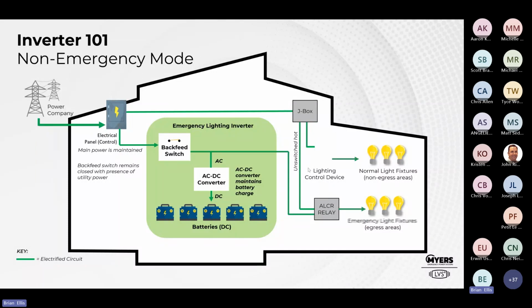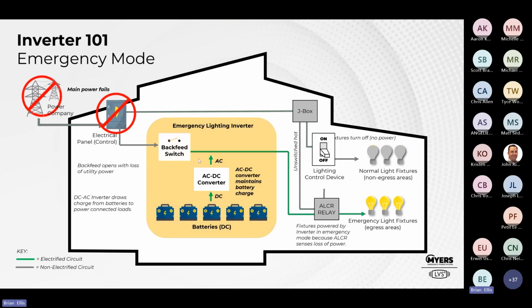So this works great. And then what happens is the switch allows it to turn on and off both until utility goes away. Our backfeed switch pops open so we don't backfeed power into the system. And now we're outputting AC power. The device says, I ignore the lighting control. Doesn't matter if this is on or off, the emergency lighting is going to be on. So this is a basic idea of how the ALCR or bypass relays function.